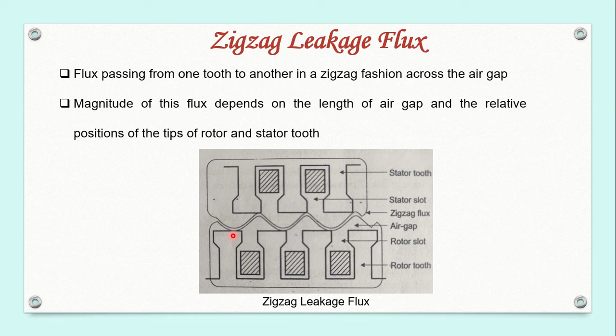To move across the air gap, it has to move from the stator to the rotor and from the rotor to the stator. So zigzag leakage flux is the flux passing from the top of one tooth to the top of another tooth in a zigzag fashion across the air gap. So the flux passing from the stator tooth to the rotor tooth, and from the rotor tooth to the stator tooth across the air gap, is the zigzag leakage flux. The amount of this flux also depends on the length of the air gap as well as the relative positions of the tips of rotor and stator teeth.